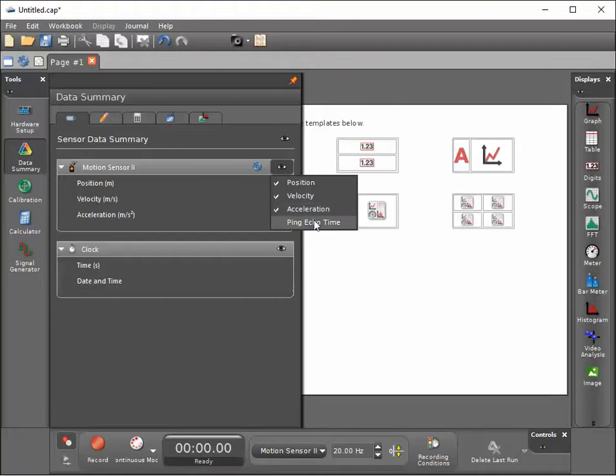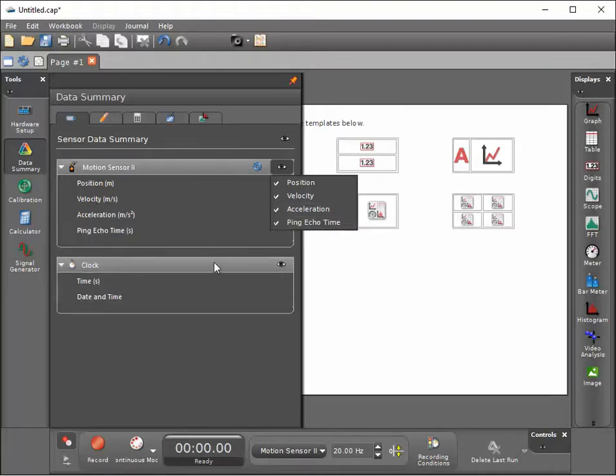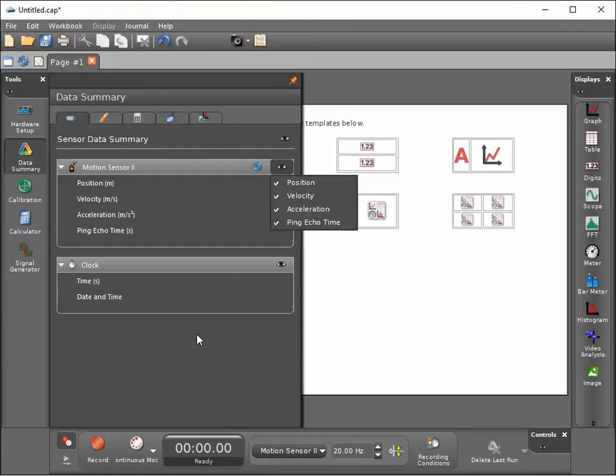From this I can select the ping echo time, and then that will display the time it takes for the signal to go from the transducer out to the object of interest and then the time for it to be reflected back to the transducer.